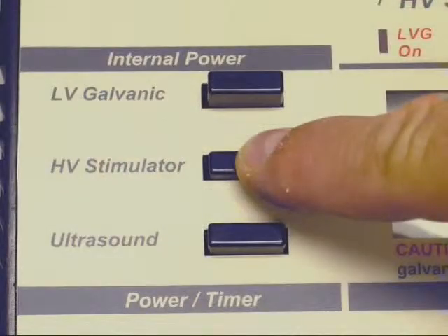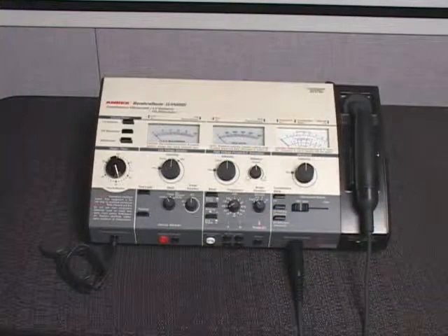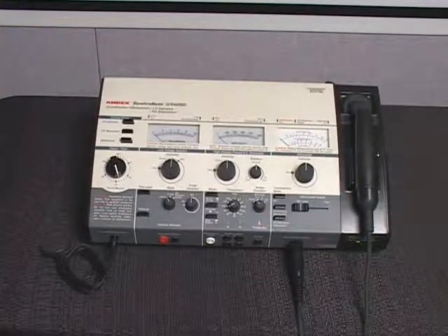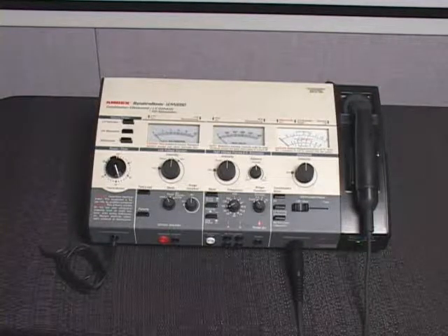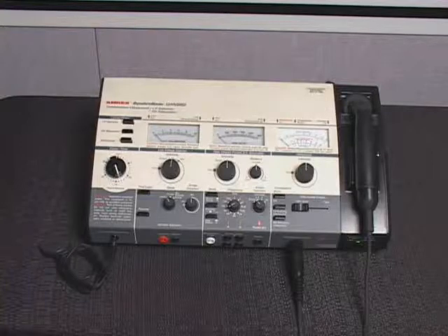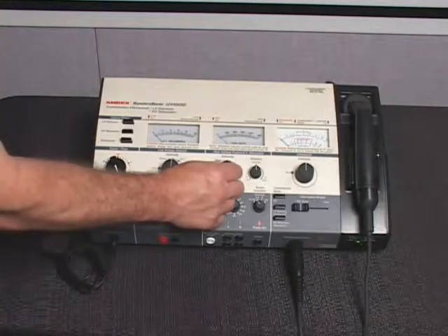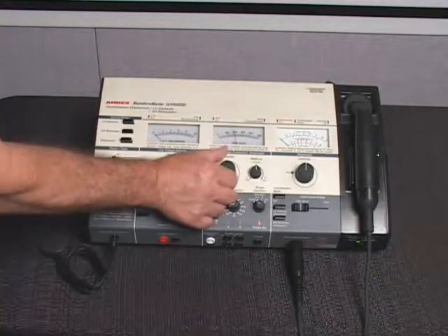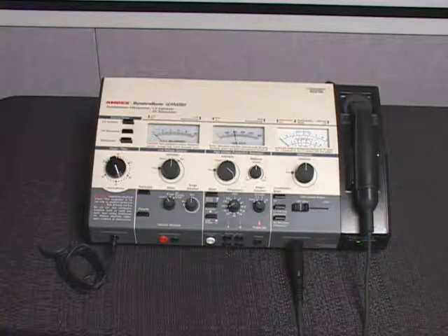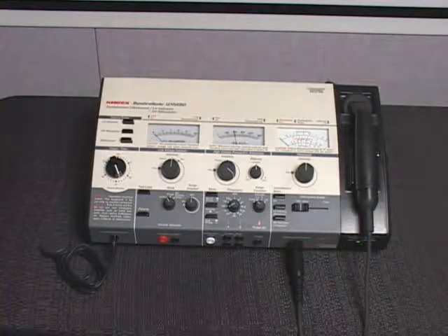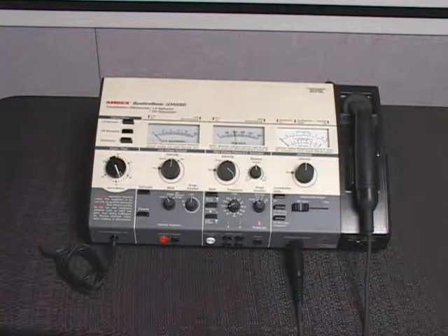Depress the internal power high-voltage stimulator switch to the on-down position. The high-voltage stimulator on indicator light, located above the upper left corner of the high-voltage pulsed DC stimulator meter, will illuminate. The output rate A and B indicator lights or the probe on indicator light will illuminate. Slowly increase the intensity control to the desired output level. If the high-voltage stimulator reset intensity indicator light is illuminated, no output will be obtained until the intensity control is returned to the zero reset position.